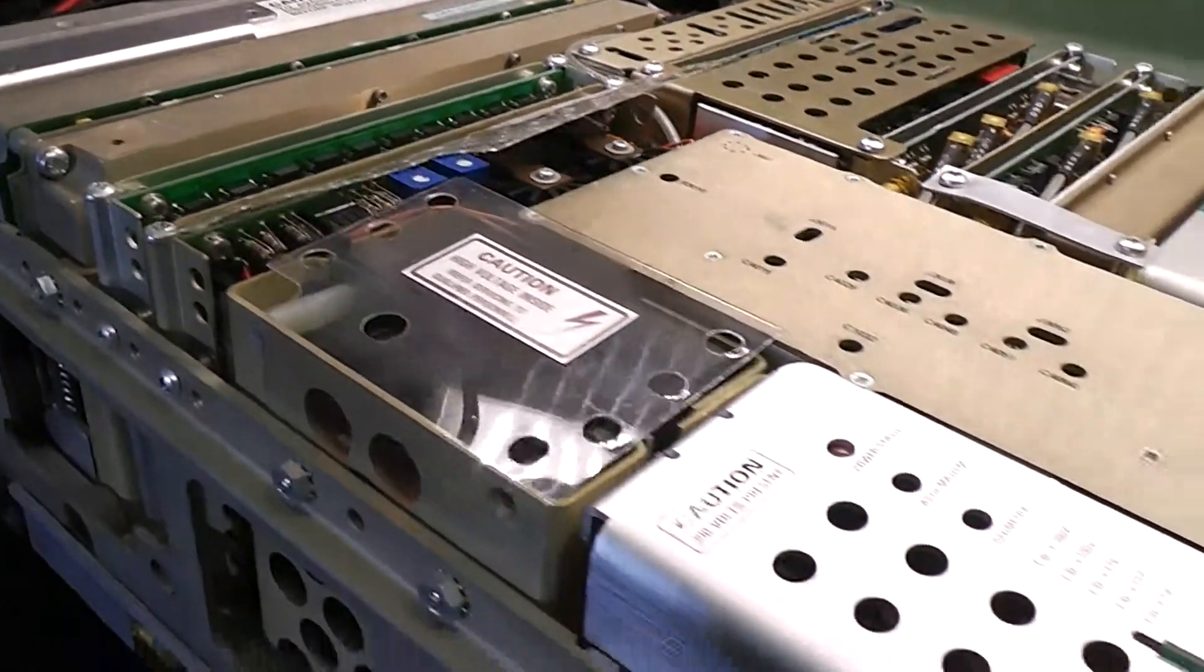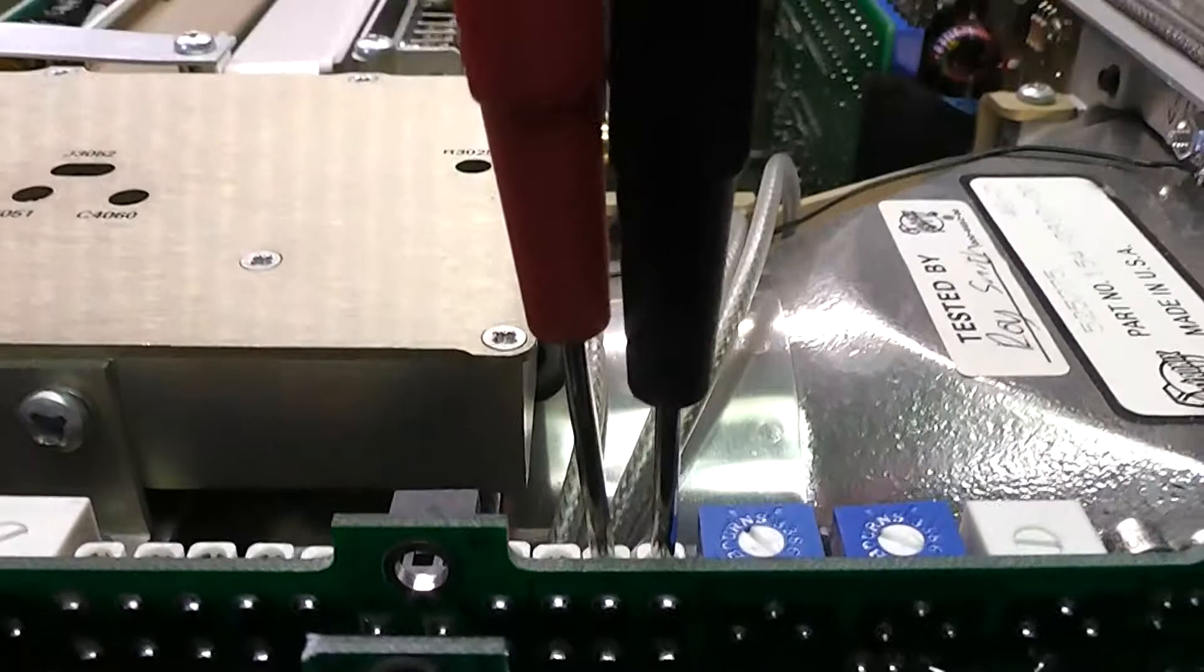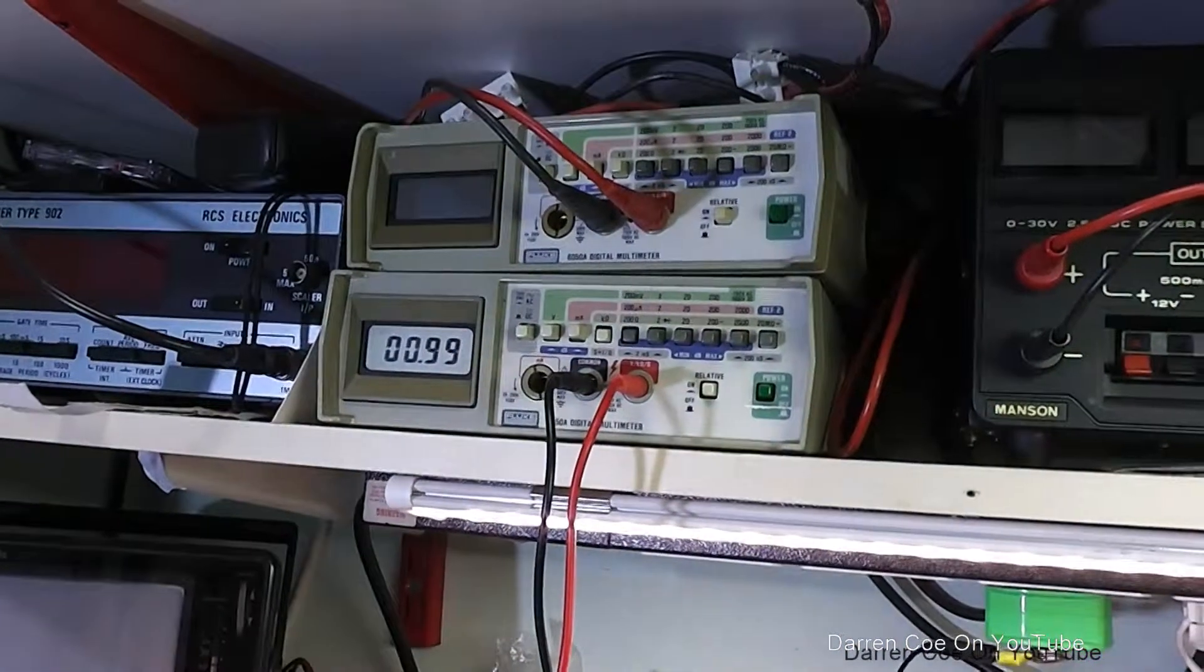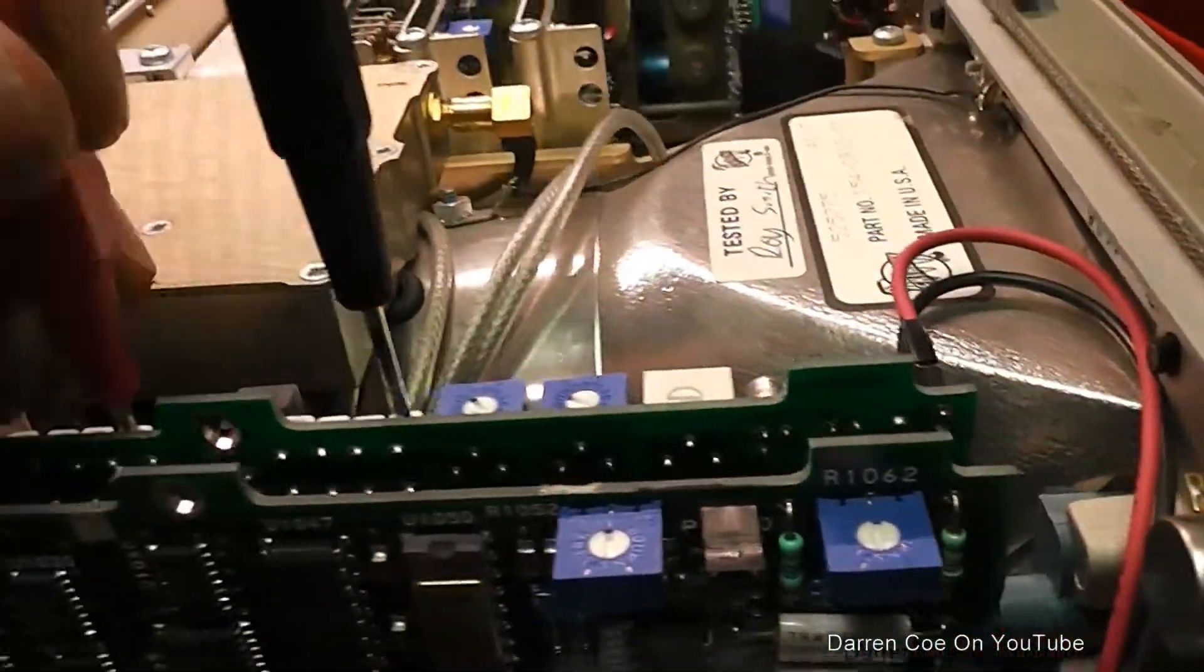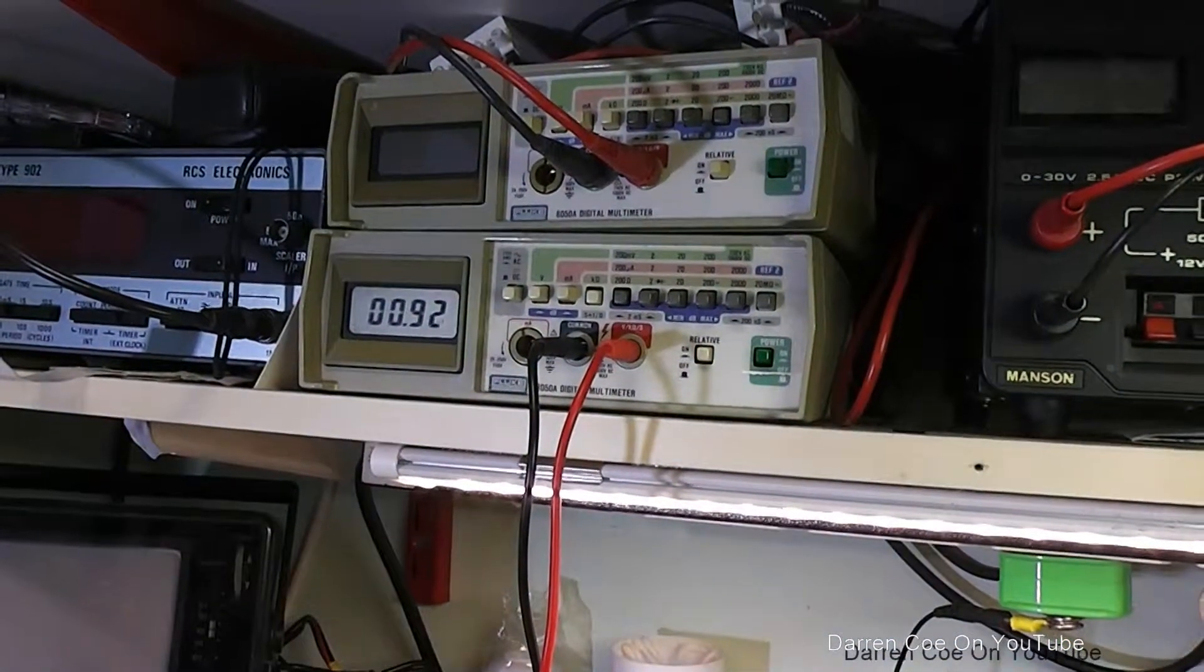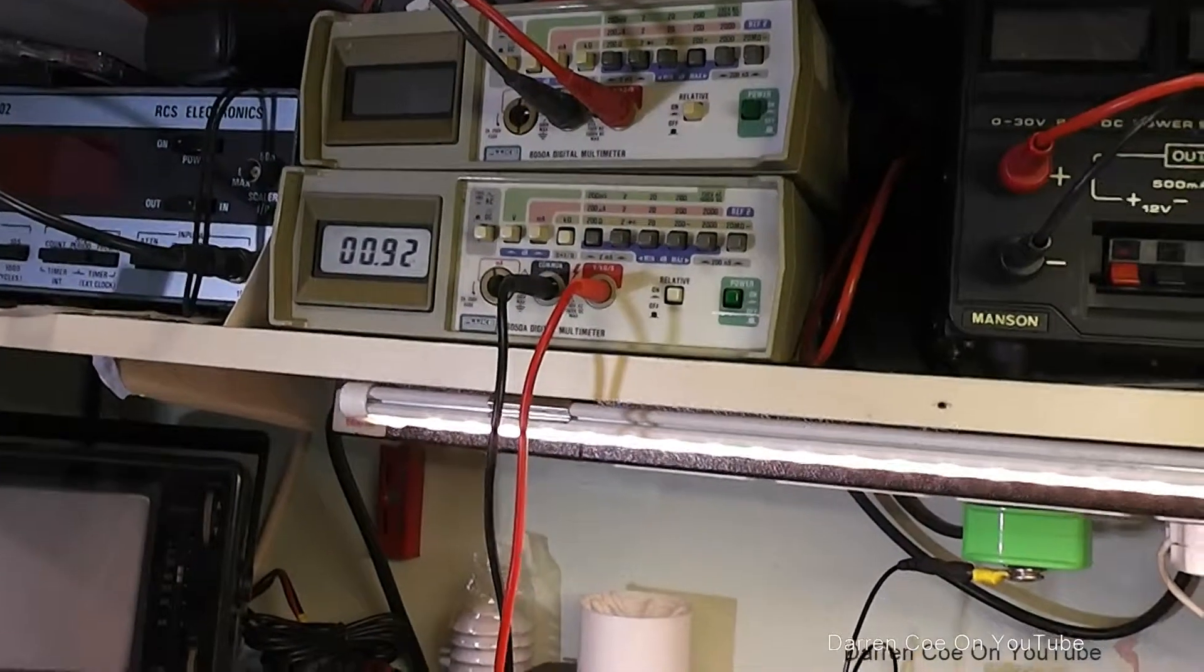I'm just doing some simple ohm meter tests across the test points of the power supply and already I can see that there's a fairly low resistance across the minus 15, that's just one ohm. Switch it to the plus 15 and again pretty low resistance there, so it is possible it's not the power supply there's actually a short.